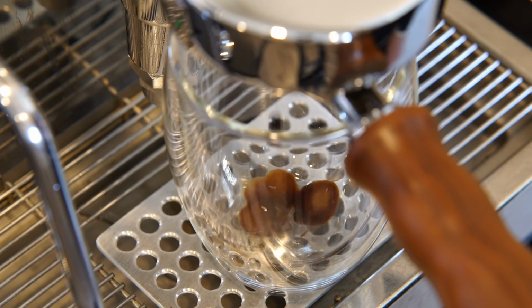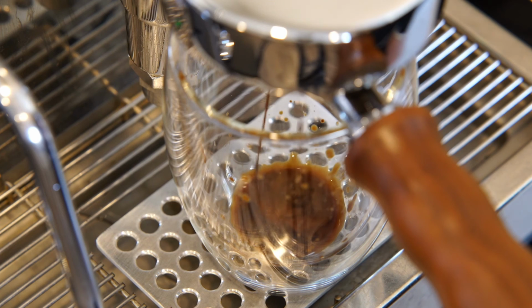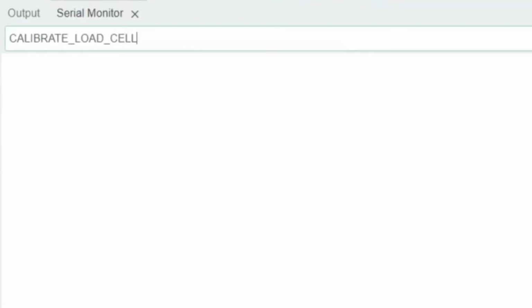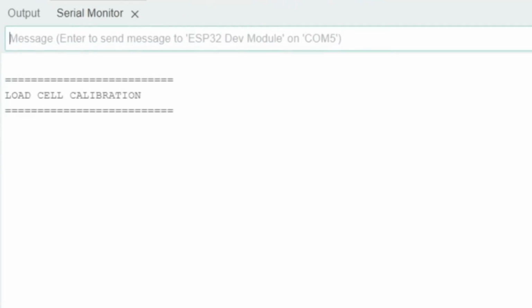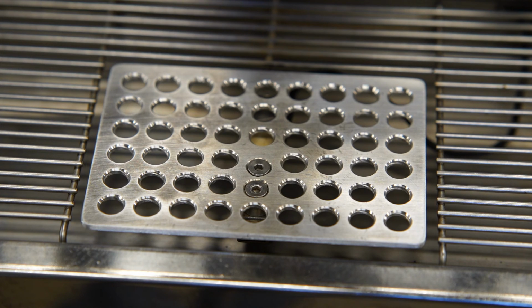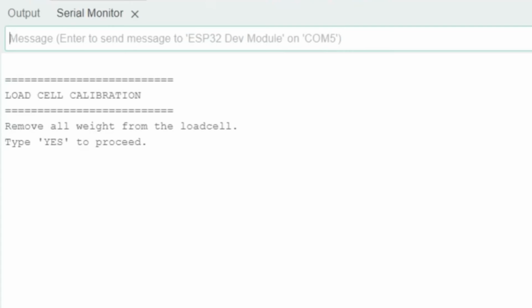Now I can calibrate the load cell, which is by far the easiest sensor to calibrate. To start, I send the command calibrate load cell. First, I'm asked to remove all weight from the load cell. Currently there isn't anything on the load cell, so I can proceed by saying yes.